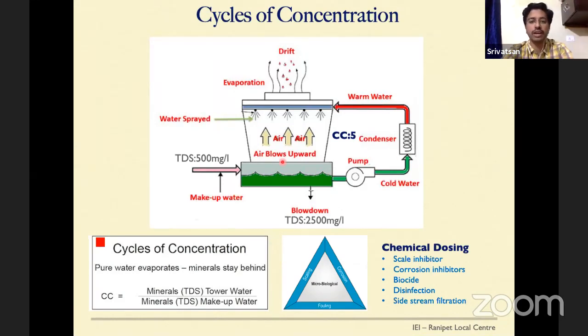Basically, all the materials are susceptible to scaling and corrosion. So we need to dose scale inhibitor and corrosion inhibitor, and we maintain some concentration in this water so that it does not affect any of the equipment in the cycle. Then, to avoid this biological growth, we dose biocide. Additionally, we do disinfection by providing some concentration of chlorine or hypochlorite.